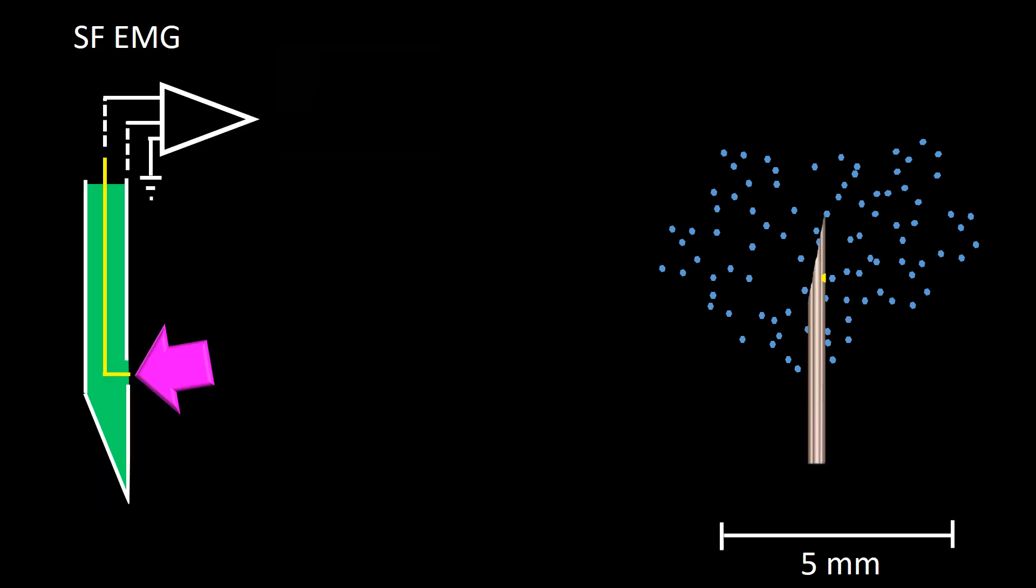The single fiber EMG needle consists of a very thin electrode with its surface on the side about 7.5 millimeters from the tip of the electrode with a diameter of 25 micrometers and a cannula which is used as reference.